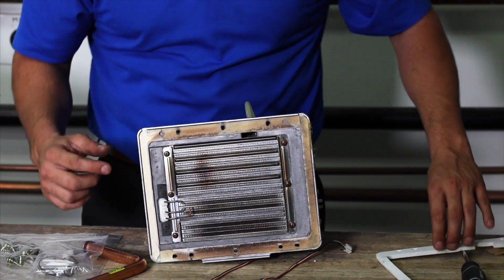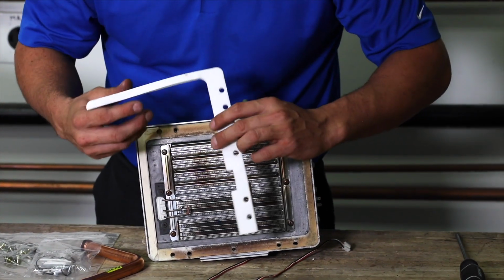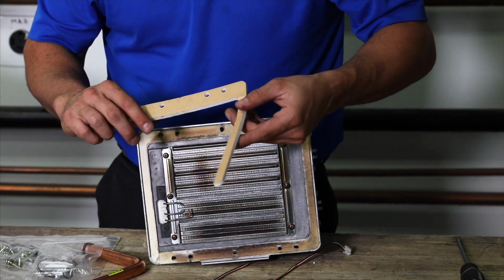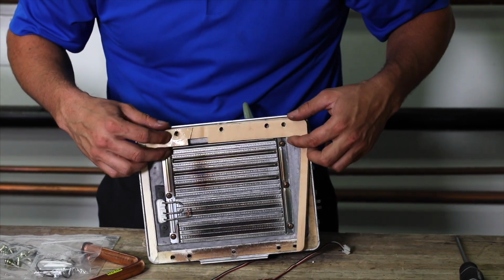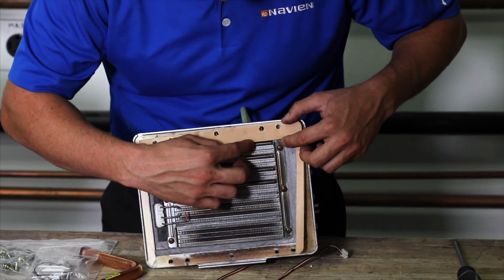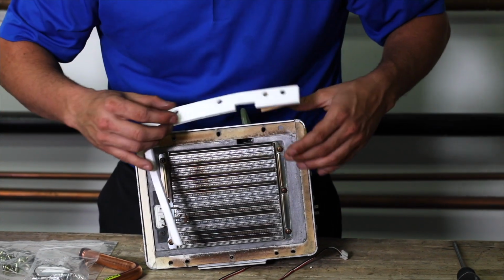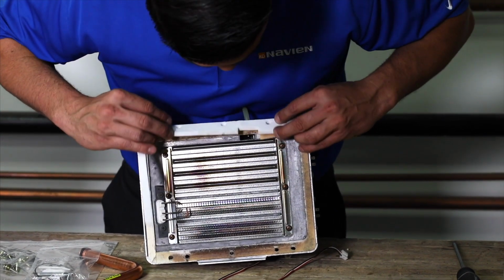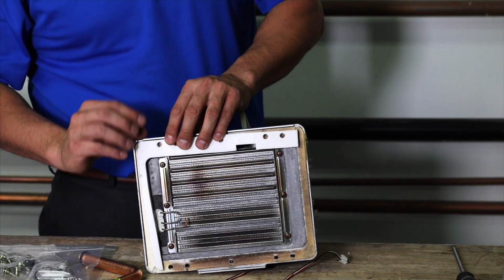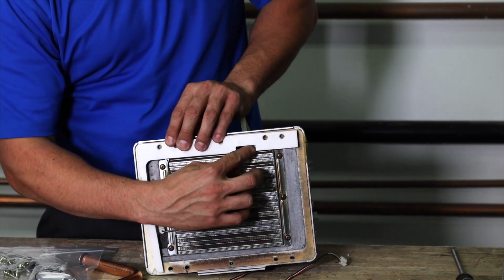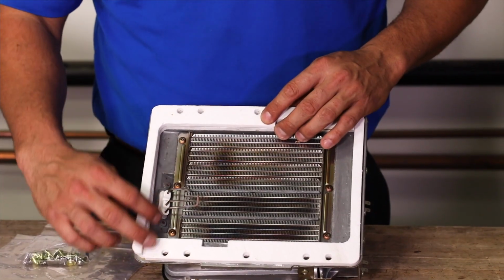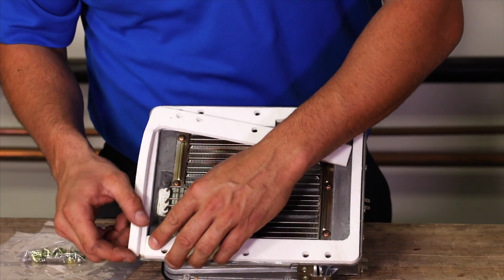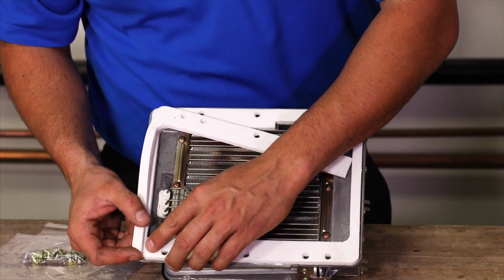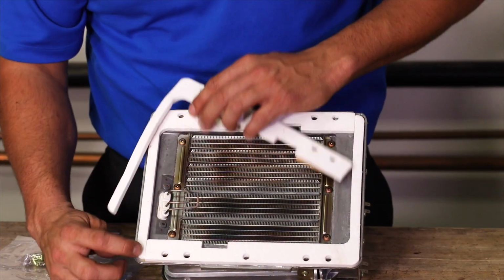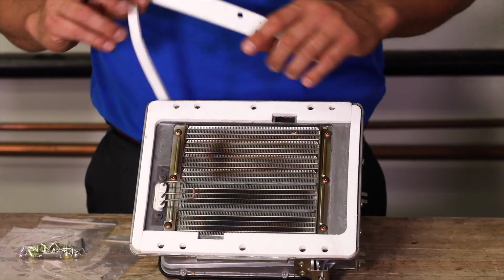Now if you were to install your gaskets to the heat exchanger, when it bolts up, it's going to cap that hole. So that's why you want to make sure that when you put it on, you attach it to your burner and that hole still stays open. Also, in these corners, you want to make sure you butt the seal to the other seal as close as possible so there's no air gaps, so you don't have any combustion coming out.